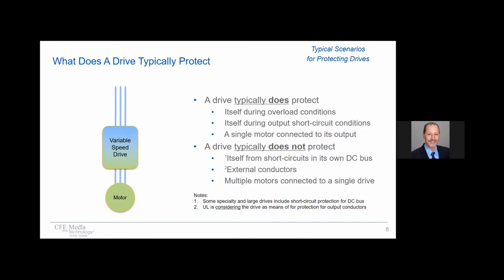There are some exceptions where there are some large and specialty drives that include built-in short circuit protection for the internals of the drive. And also the other exception would be that UL is presently considering for the future that the drive would have a means of protecting output conductors. But that again is for the future. So what generally happens is, in most cases, there is something that's required besides the drive itself, to protect itself. And that's known as an overcurrent protective device, which is a fancy term for typically breakers and fuses.